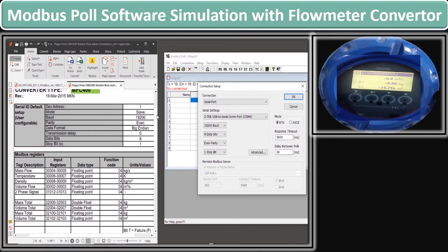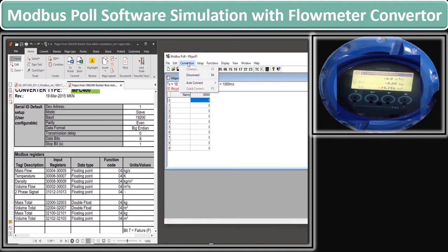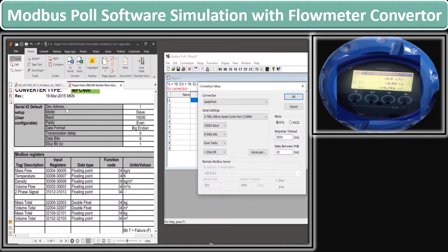We now go to our Modbus Poll software and put the default serial parameters to establish communication between the flow meter and Modbus Poll software. As we start the software, it connects the device automatically with its last parameter setting. We will first disconnect it to check and redefine our parameters. We go to Connection and click on Connect. A connection setup window pops up where we define the Serial Setup values. As you can see in the PDF parameter list, baud rate is given as 19200, so we have defined 19200 baud rate in our configuration.